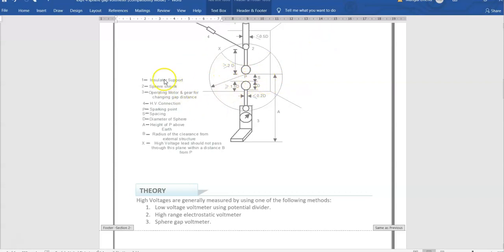That breakdown voltage will be an RMS value, measurable from the voltmeter. Now we have to check whether the calculated voltage from the Indian Standard Table is near the voltmeter reading or not. If yes, we can say the sphere gap can be used for measurement of voltage. If no, then we have to discuss why our measured value from the sphere gap is not the same as the voltmeter. Okay, so let us start the experiment.